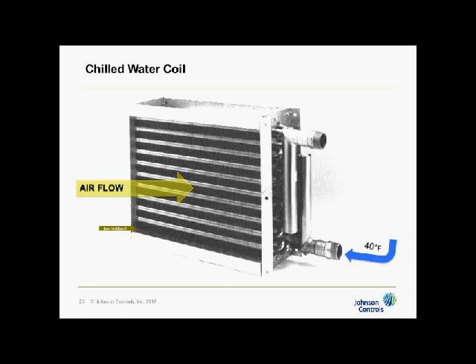The ramification of a dirty coil is that the heat transfer characteristic gets worse. And that means that my leaving air sensor that's set for 55, that controls the valve that's on this return, to let water in and out of the coil is going to open up. The valve opens because it's supposed to maintain 55 degrees. Well, when I'm at design, then I'm going to be at design GPM. But when I'm at dirty coil, then I have to pump more water through it to get the same work out of the coil. Even though the load hasn't changed, the work through the coil has. It just can't do as much without more water, so we increase the flow.